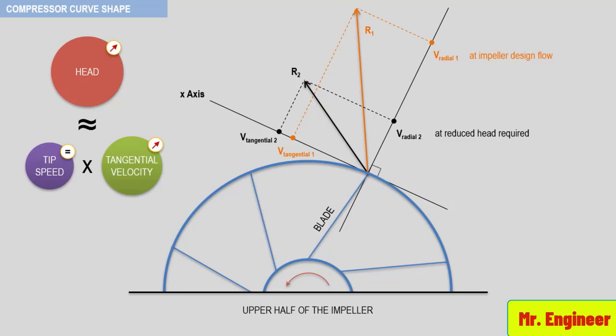Practically, this makes sense: the slower the gas proceeds through the vane, the more time it has to pick up energy imparted by the blades, and as a result will increase the energy or head produced within the impeller. Therefore, for all dynamic blades and impellers that increase the energy of the fluid by the action of the vane on the fluid, they can increase fluid energy only at a lower flow rate, assuming the speed of the impeller and the inlet angle of the fluid to the blade remain unchanged.